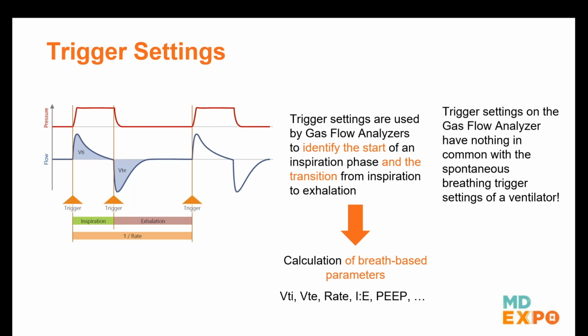So for example, our ones have a small T that flashes up on the display each time the device is triggering. If you see that your analyzer is not triggering, that means your trigger settings are off. We talk about two triggers. One is called the start trigger. That one we will set in a way that we can detect when an inspiratory phase starts. And then there is also an end trigger, or sometimes they call it stop trigger. That's actually when the inspiratory phase ends, and that means at the same time it switches to exhalation, right? So everything between our start and end trigger is inspiration, and everything between the end and the next start trigger is exhalation. And with that, the analyzer can then calculate all kinds of stuff.